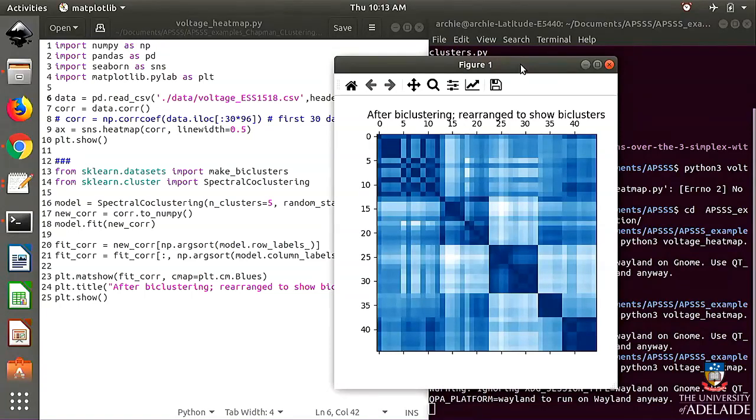the voltage decrease relative to the current increase is much larger than everybody else, and that usually throws grouping algorithms into a bit of disarray. It thinks, okay, there's actually now 4 or 5 clusters, not 3, and it's useless. So that's usually a telltale sign for us that something's wrong with that particular customer rather than the rest of that group.